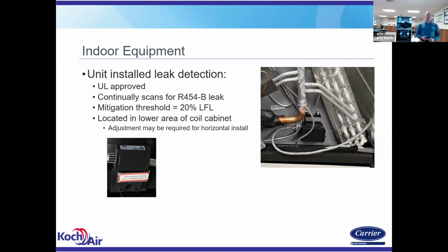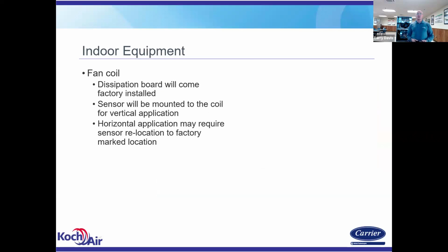There is a factory designated location for the sensor. And if you have to reposition that sensor because you're in a horizontal application, instructions will show you exactly where to mount it. Again, on a fan coil, the dissipation board comes factory installed, the sensor's already mounted on the coil, and you'll have to relocate it for all horizontal.